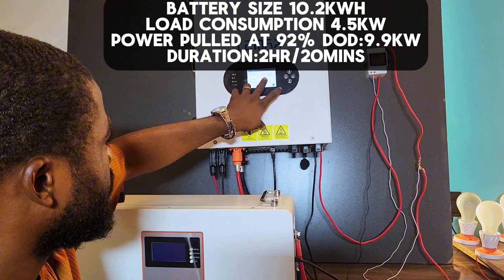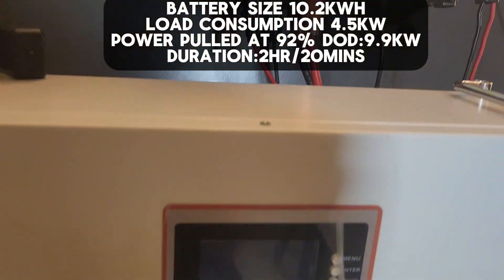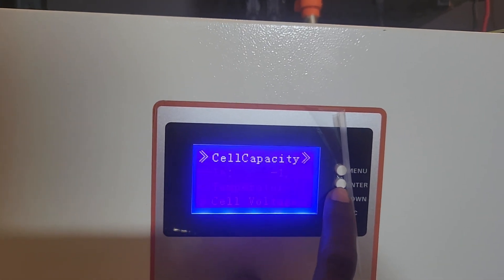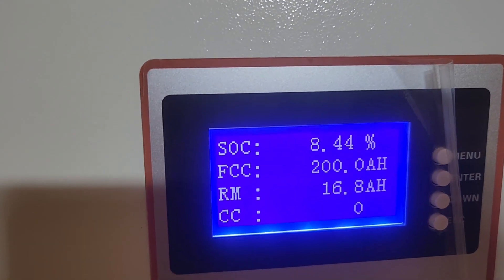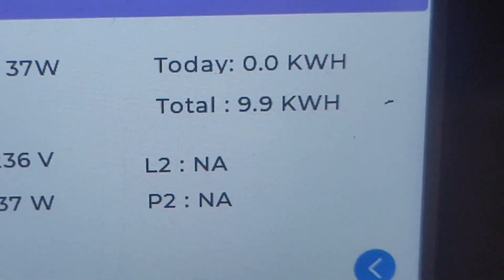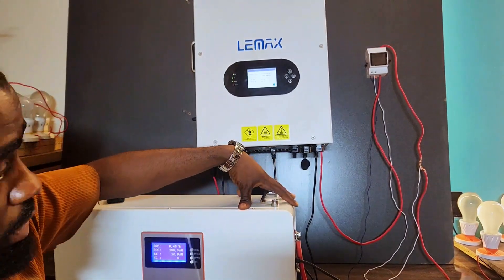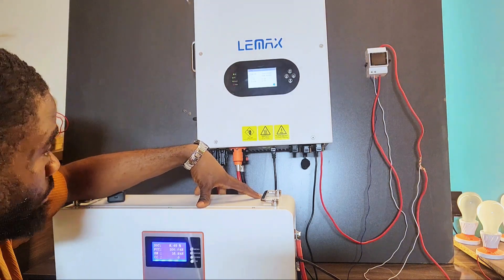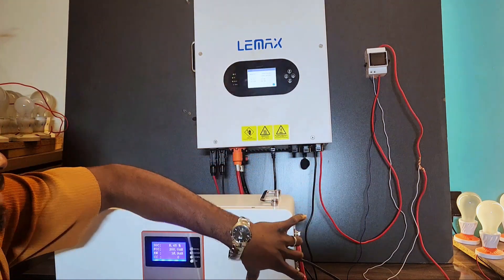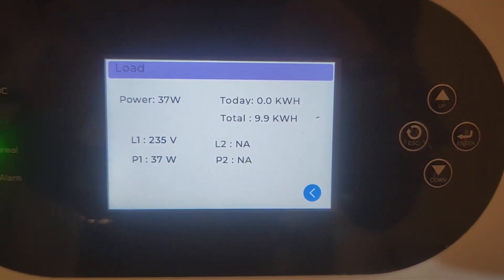On the inverter screen, the total energy consumption is 9.9 kWh — that is 9,900 watt-hours consumed from this battery. On the battery bank, we still have about 8% remaining. So at 92% DoD, we consumed 9.9 kWh. The conclusion is that the Lemax 10 kWh lithium battery is up to rated capacity. If we were to pull out the remaining 8.45%, we would get at least 10.1 kWh or more, consistent with the rated 10.2 kWh.